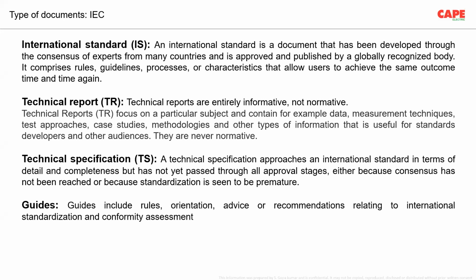Now, to make a background, I'm just explaining what kind of standards are available from the standard publishing body. I'm just taking the example from IEC. IEC has the international standards. That means it's a rule. Technical reports are not normative. It is not a rule. It is just for information. Technical reports, also technical specifications. If you see an IEC standard with the code TR or TS, you should understand that these are informative, or these are actually supporting some of the standards.